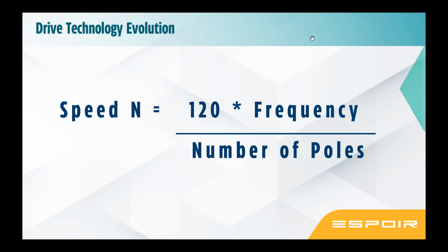So how does a VFD work? The AC induction motor speed principle formula is 120 into frequency divided by the number of poles. The standard design of the number of poles is in pairs of 2, 4, 6, 8, 12, and then multi-pair pole motors. Now, the number of poles you cannot change. Once it is designed, it is impossible to change. There are dual speed motors and triple speed motors available where a set of windings can change, but again it is step speeds. You can have 2 or 3 maximum standard speeds. You cannot change the speed linearly. You cannot change the speed dynamically.